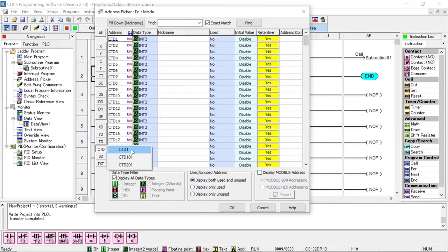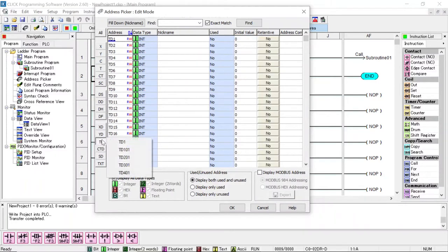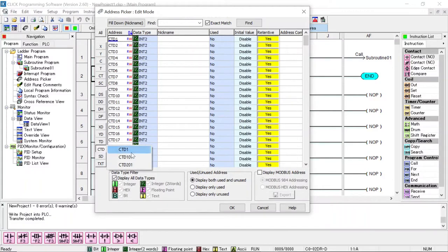And the same is true down here for the counter datas. You have a counter data word for every counter. Now, notice also these are INT2s. That means these are double words, whereas on the timers, they're just single words. You can only go up to 32,000 something on a timer value. So if you needed something longer than that and you're in seconds, you would need to change to, say, minutes and divide by 60 or whatever. But the counters can go up to a much, much higher number, and you can see that these are all double integers, so they go to 32-bit words.